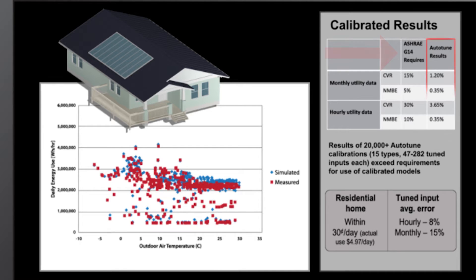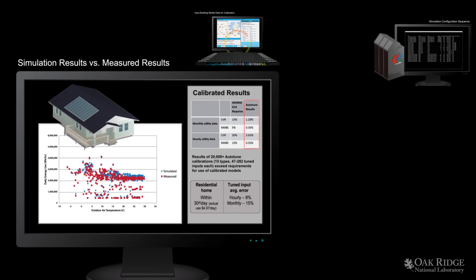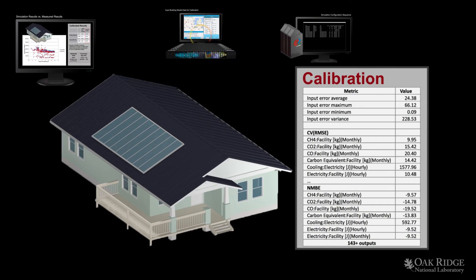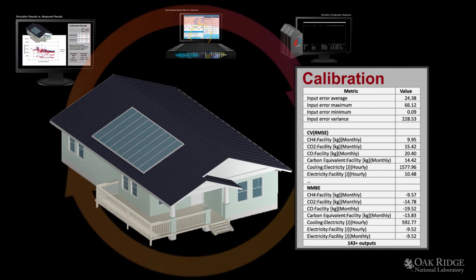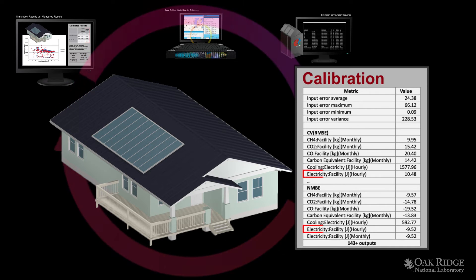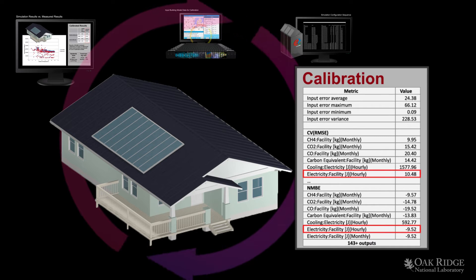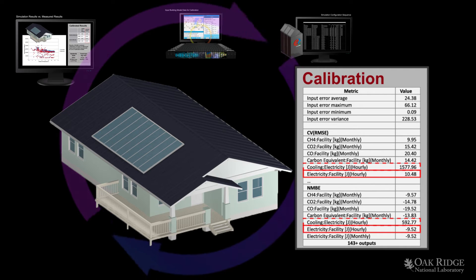A document known as ASHRAE guideline 14 specifies the criteria for a legally useful calibrated building model, requiring less than 30% error on hourly data. Using supercomputers, AutoTune calibrated over 20,000 building models and averages an error below 4%, far surpassing requirements used by energy service companies, electrical utilities, banks, and the Internal Revenue Service.